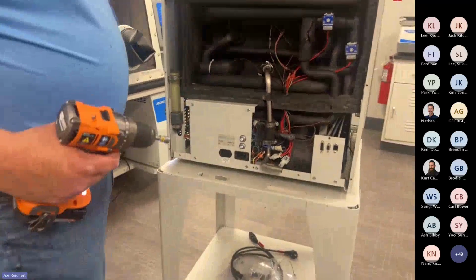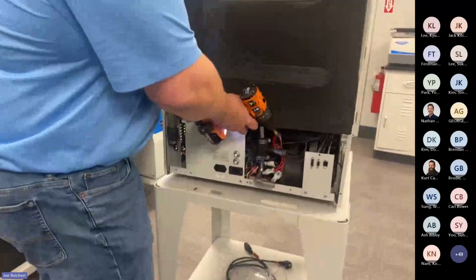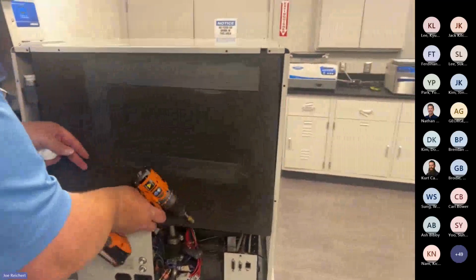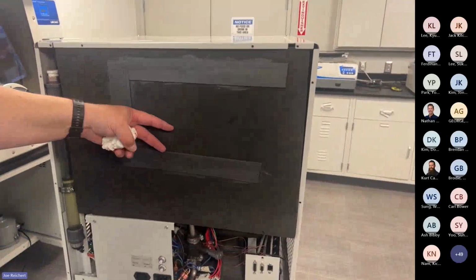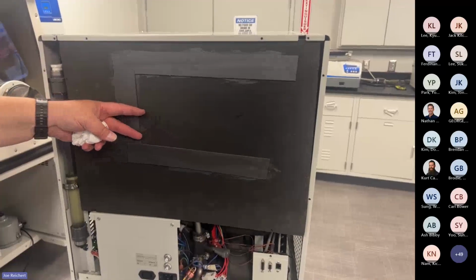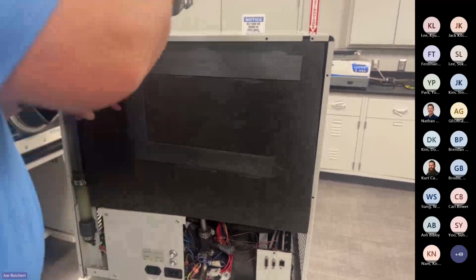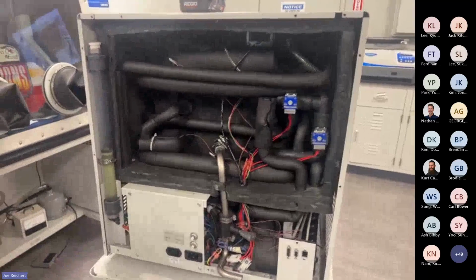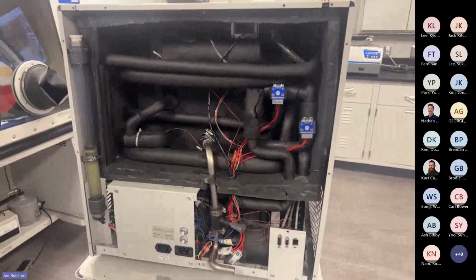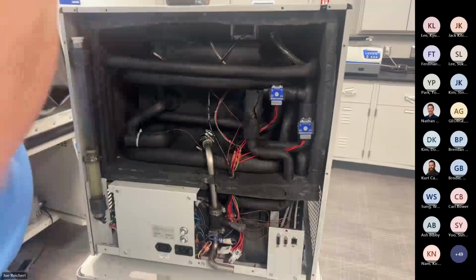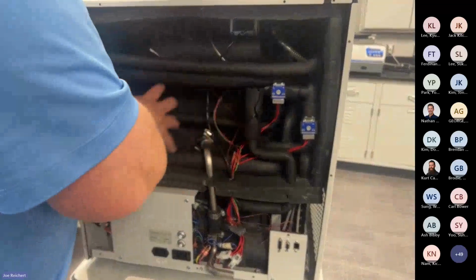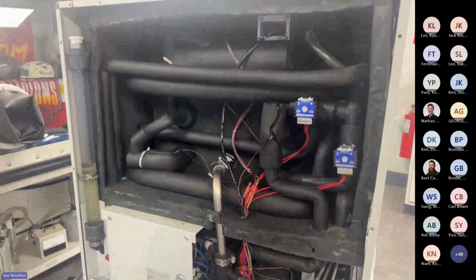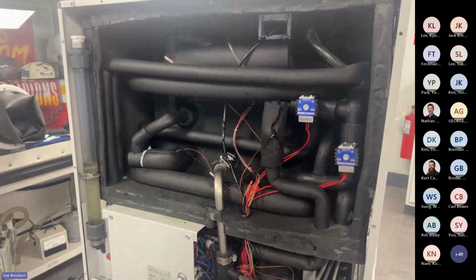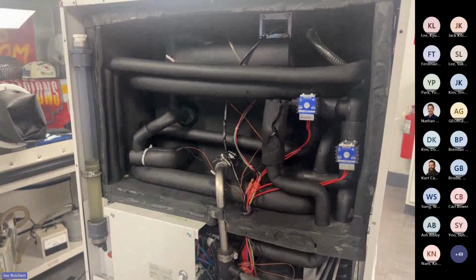So again, this panel will sit just like this on the backside, covering it up. It has to be completely sealed in the back from air getting in here. Even though these pipes on the inside are already insulated, it gets so cold that you will still get a ball of ice. I've seen this entire area full of ice before.